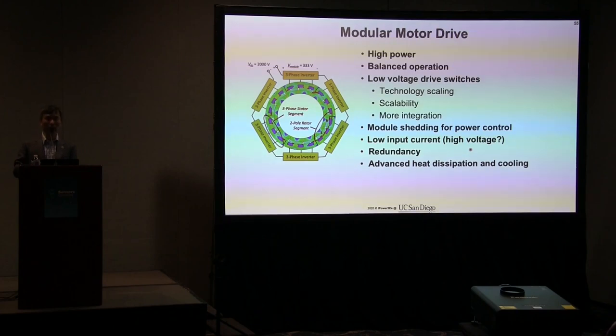There's an emerging approach in modular motor drive, where the motor is divided into multiple sections connected in series. Each section now occupies a smaller voltage fraction. For example, each section might be 330 volts, and stacking six of them together gives us 2000 volts at the input. With this stacking and assumed balanced operation, we get lower voltage stress on the switches, which benefits from technology scaling.